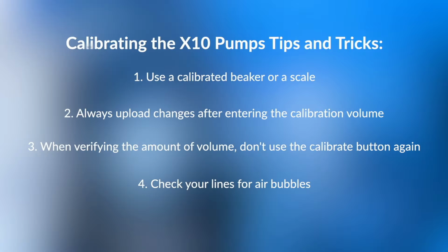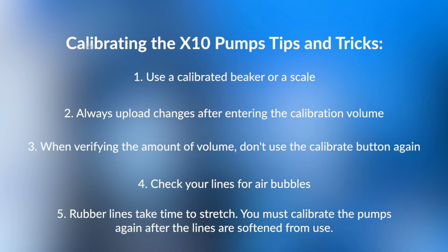And the last tip is about the rubber lines in the dosing heads. When you first get them, they're pretty stiff. They're hard, especially during the winter time, they could be really hard. So if you run that pump when the lines are stiff, your calibration is going to be one way. Once the heads have been running for a while, that line, because it's a rubber line, will eventually give and settle into a nice malleable line that is soft. So the calibration that you did when the lines are hard is completely different than when the lines are soft. I recommend that you calibrate the dosing pumps again a few days later, after the unit has done several tests, to make sure. Now the lines are nice and malleable.